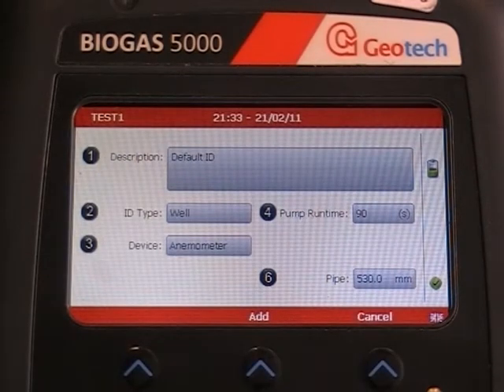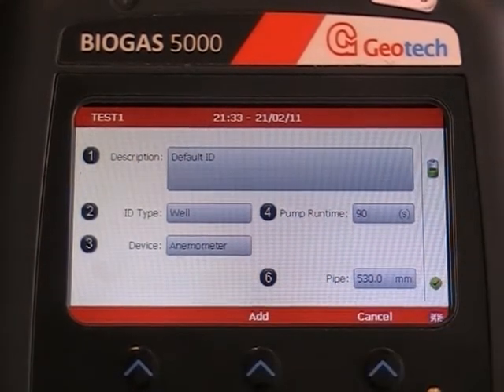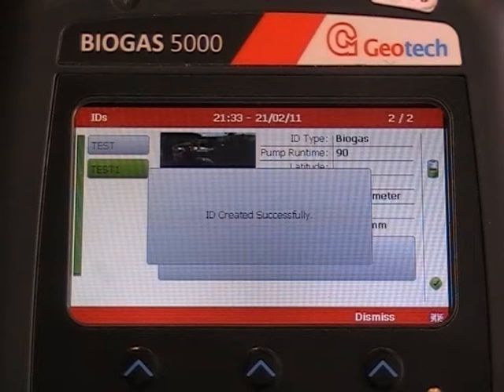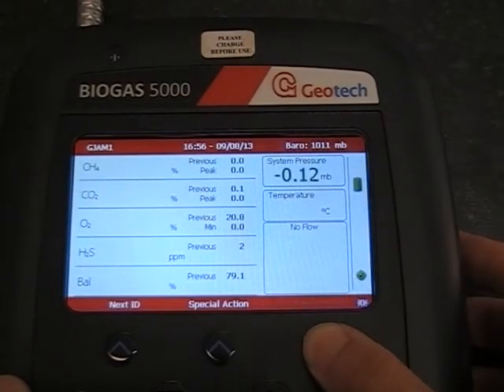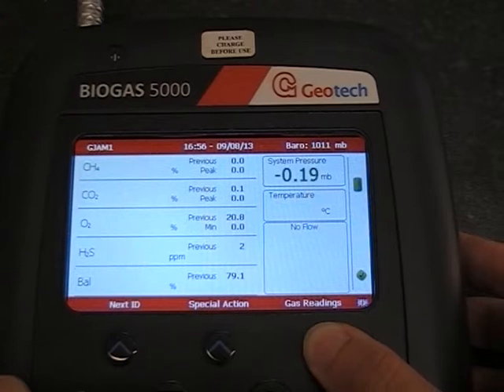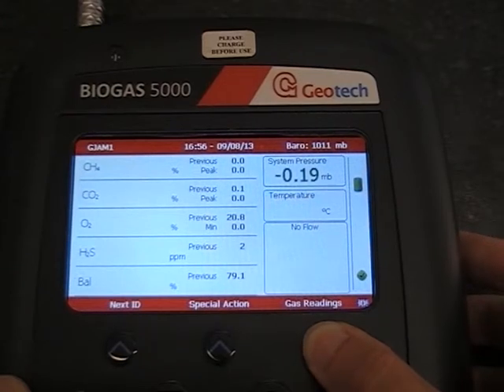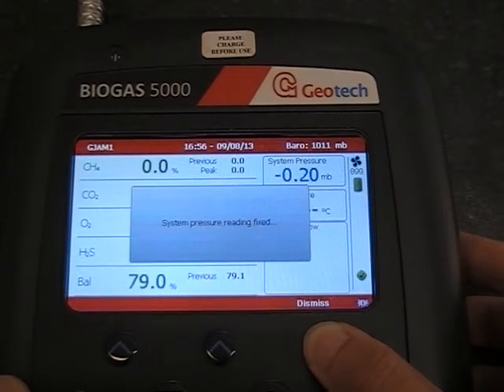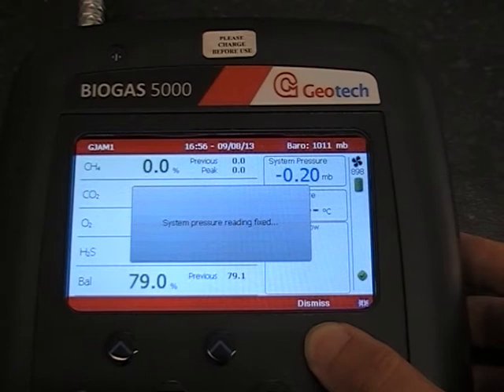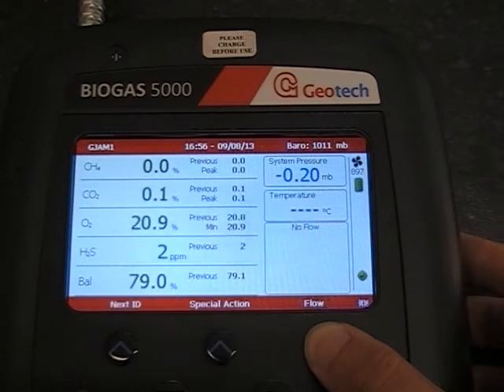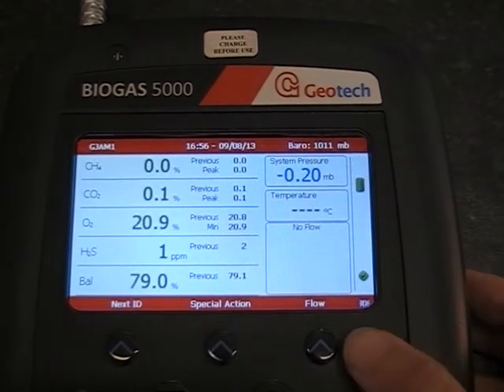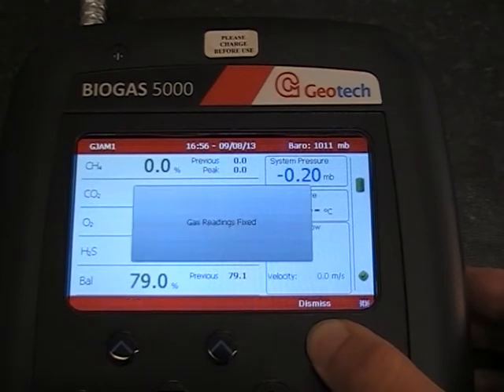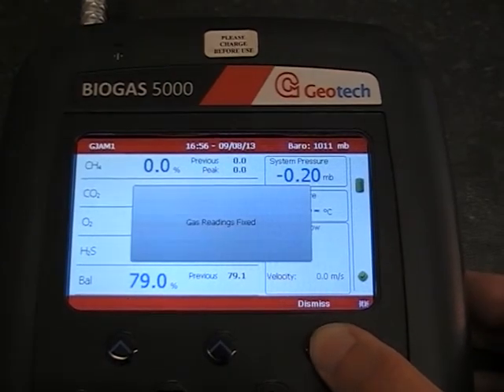Then press Add and select Return to use your ID. From the main gas read screen, press System Pressure. When the pressure reading has stabilized, press Gas Readings to fix the pressure reading and take a gas sample. When the gas readings have stabilized, press Flow to fix the gas readings and take a flow measurement.